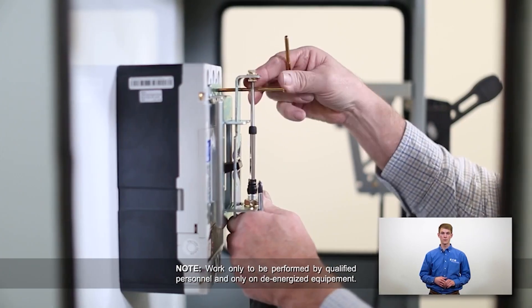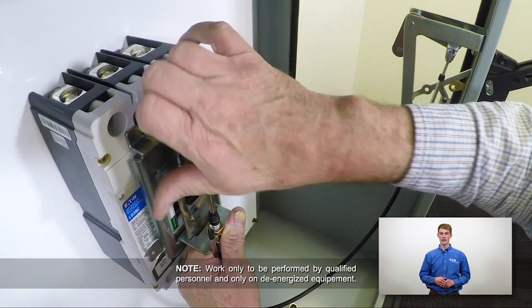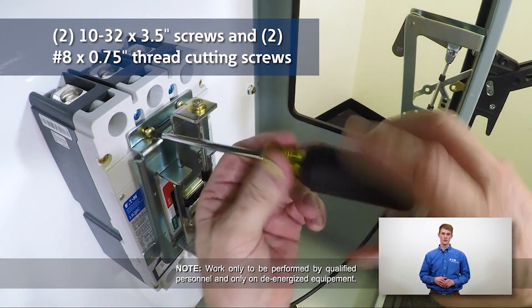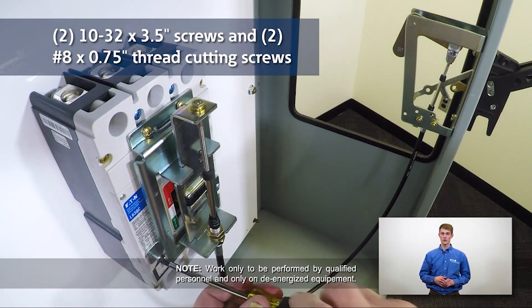Place the actuator on the front of the breaker and orient the slider so that the slot captures the breaker handle. Fasten securely with the two 10-32 3.5-inch screws and two No. 8 0.75-inch thread cutting screws.